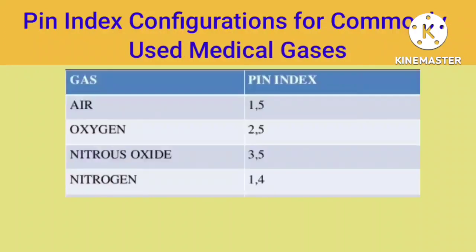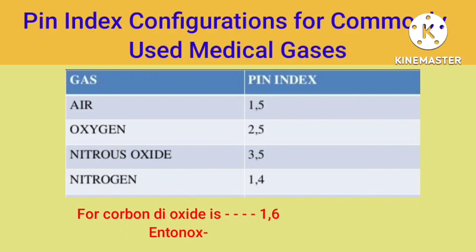Pin Index Configurations for Commonly Used Medical Gases: Pin Index for Air is 1 and 5; for Oxygen, 2 and 5; Pin Index for Nitrous Oxide is 3 and 5; for Nitrogen, 1 and 4; for Carbon Dioxide, 1 and 6; Entonox, 7.